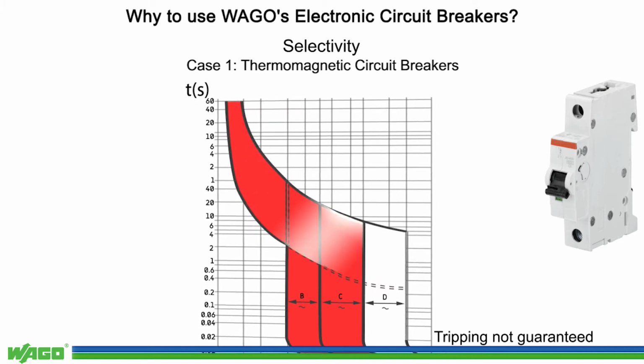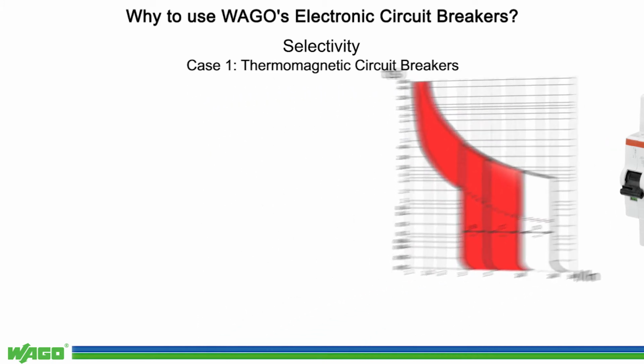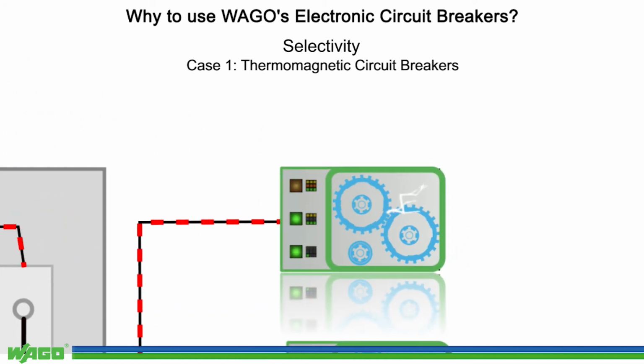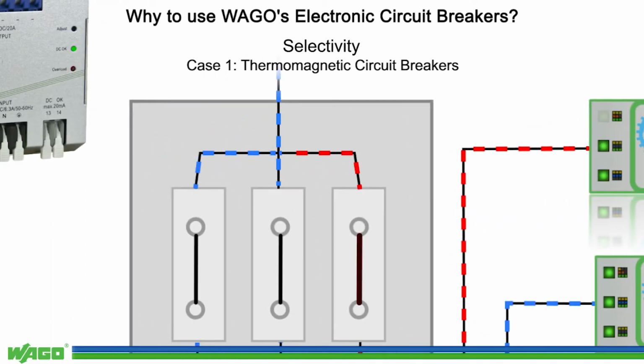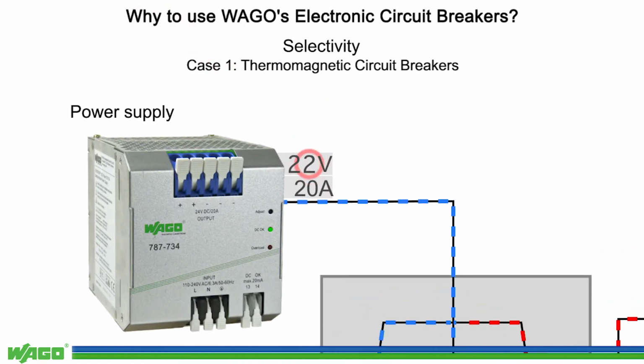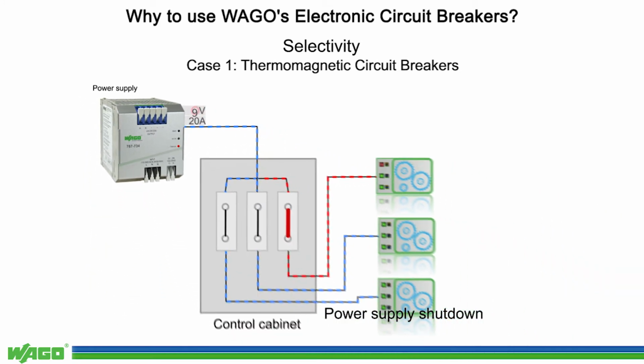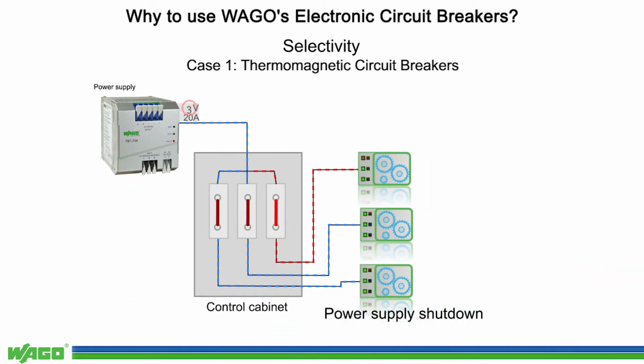In fact, thermotripping of thermomagnetic circuit breakers takes too long to shut down overloaded channels. As a result, the upstream power supply unit activates its overcurrent protection and reduces its output voltage. This can cause the entire control cabinet to shut down.